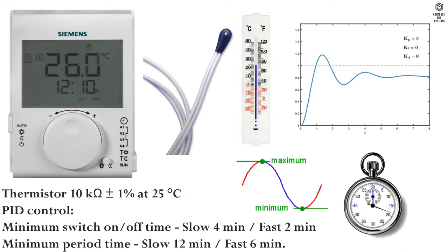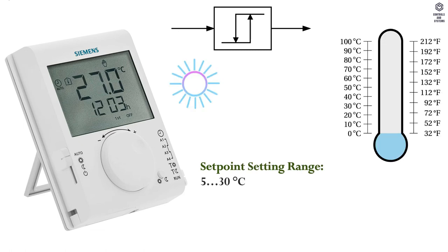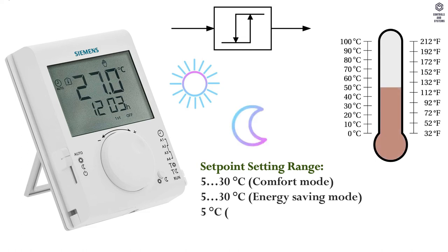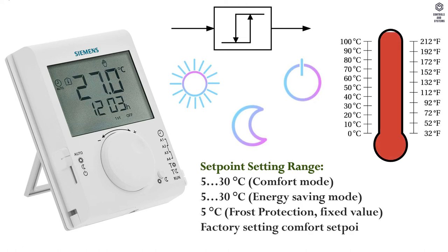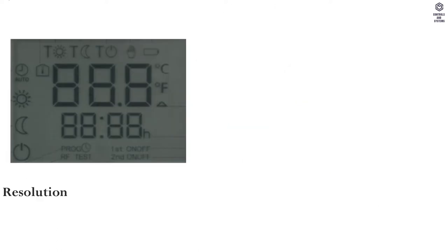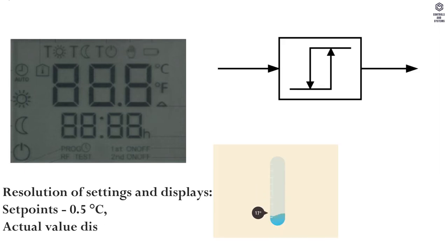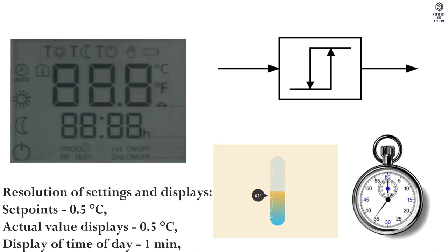Minimum period time: slow is 12 minutes, fast is 6 minutes. Set point setting range: comfort mode 5 to 30°C; energy saving mode 5 to 30°C; frost protection fixed value at 5°C. Factory setting comfort set point is 20°C; factory setting energy saving mode is 10°C. Resolution of settings and displays: set points 0.5°C, actual value display 0.5°C, time of day display 1 minute.